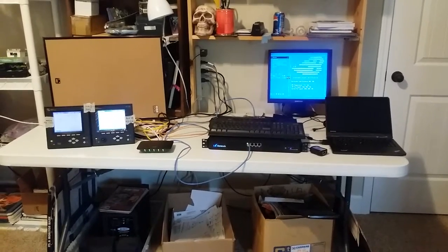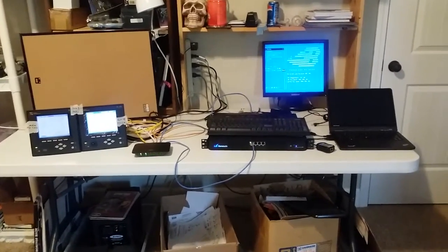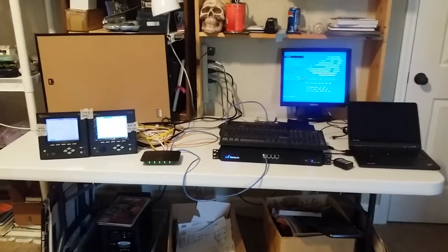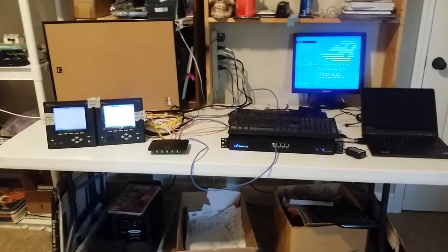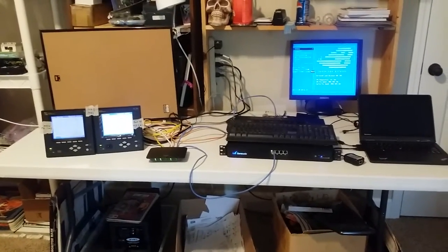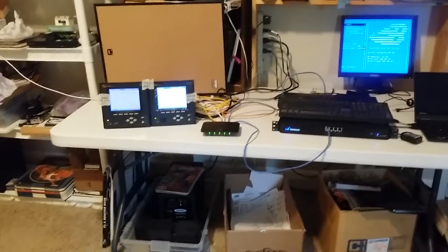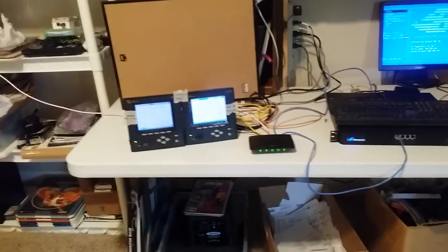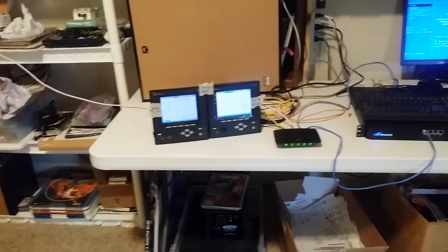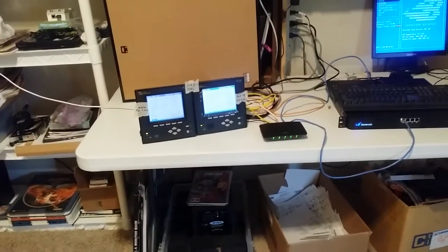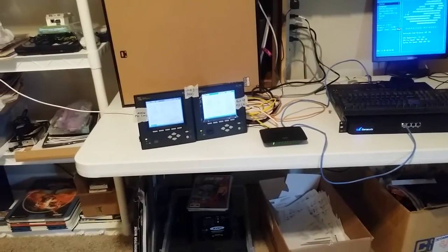I wanted to put together this quick proof of concept demo showing a Barracuda load balancer 340 successfully being used to provide control PLCs the ability to failover to a backup standby PLC when the PLCs themselves don't have a native ability to hand off their network connection parameters.